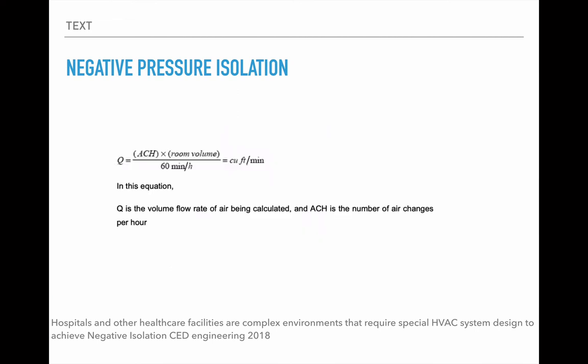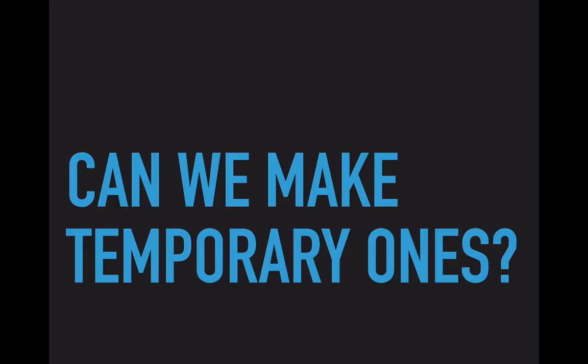And this is the equation for flow. I would recommend an engineering degree, or you can be like me and have no life, and then you'd understand it. So ACH is basically how many cycles, the number of air changes that happen within the room per hour, times the room volume over 60, which will give you the setting for the actual HVAC system.